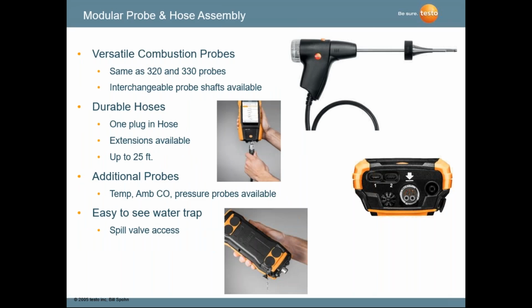One of the things that's overlooked a lot too is the probe assemblies. These probe assemblies, whether using Testo or another instrument, take a lot of beating. They're put in stacks, high temperatures, 500-600 degree temperatures, hot, wet, dirty flue gases. We've been using our standard probe, which is really a nice probe for commercial and industrial applications. As you can see there, we have interchangeable probe tubes at the top. The hose is one hose. The hose connects to the bottom of the instrument, and everything is internal in that one hose, so you don't damage the thermocouple wire that goes from the tip of the probe to the base of the instrument.